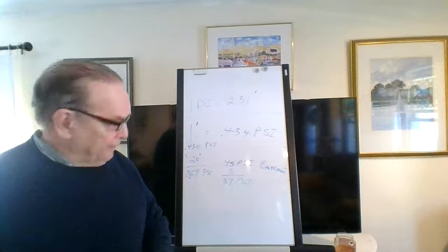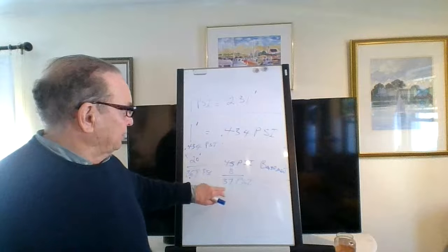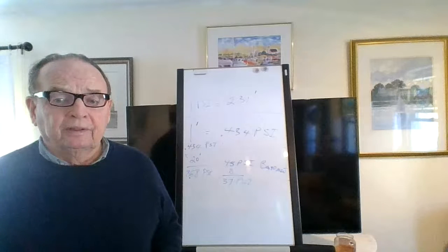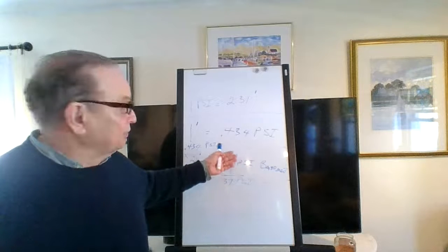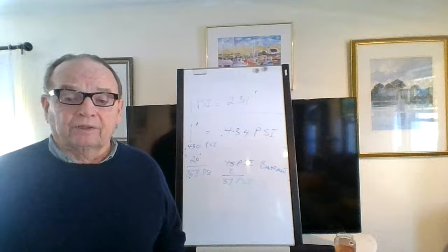So we got 37 PSI. That is a difference, right? If you drop the pressure from 45 down to 37, it would be noticeable. And you might have a customer that would pick up on that. And you could explain to them, the reason for that is this, right? Water has a higher pressure, the lower down you get.